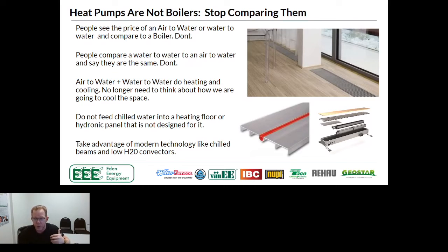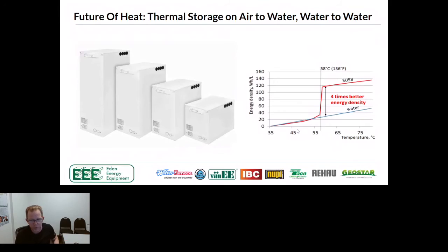Do not feed chilled water where you're not supposed to feed chilled water. And take advantage of some of the modern technology that's available to you so that you can do cooling. Don't dismiss the fact that you can really, really easily do hydronic cooling in a house using a convector. Again, here you can see a picture of the Climate Canal. There are a lot of options on the market. There is availability across Canada through all the various wholesalers that are out there. And then think outside of the box. Start to look at things like PCM batteries. So if you look at thermal storage, the idea behind it is that we can store this energy effectively for off-peak.